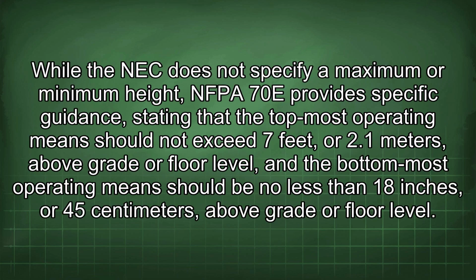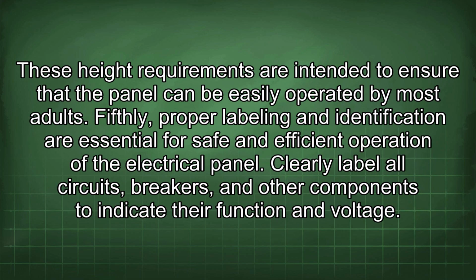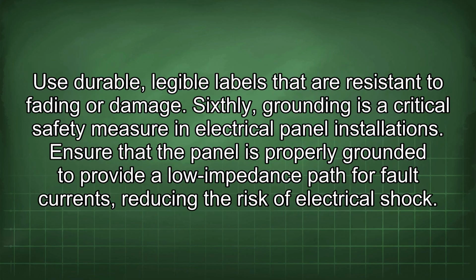While the NEC does not specify maximum or minimum height, NFPA 70E provides specific guidance stating that the topmost operating means should not exceed 7 feet or 2.1 meters above grade or floor level, and the bottommost operating means should be no less than 18 inches or 45 centimeters above grade or floor level. These height requirements are intended to ensure that the panel can be easily operated by most adults. Fifthly, proper labeling and identification are essential for safe and efficient operation of the electrical panel. Clearly label all circuits, breakers, and other components to indicate their function and voltage. Use durable, legible labels that are resistant to fading or damage.